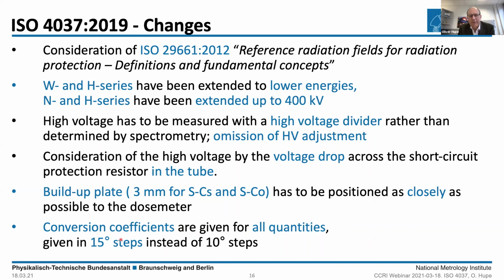And it's given in 15 degrees steps instead of 10 degrees, because for the type test requirements, you always need 15 degrees steps.